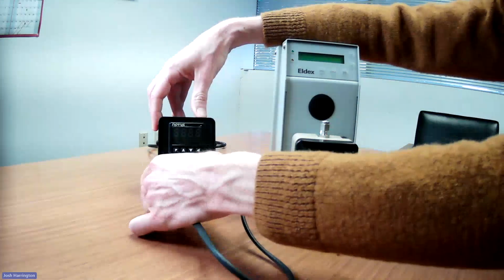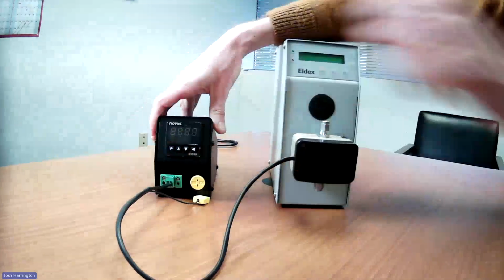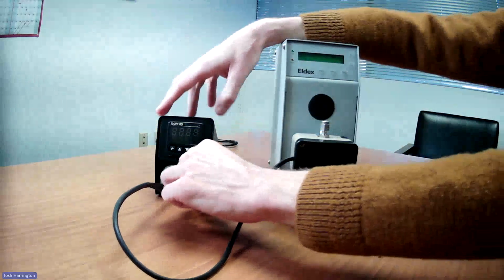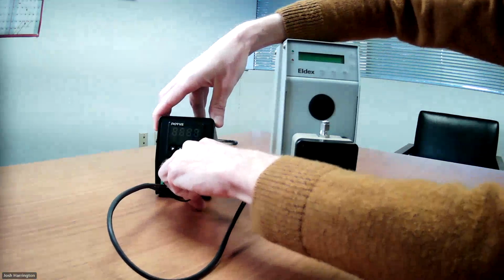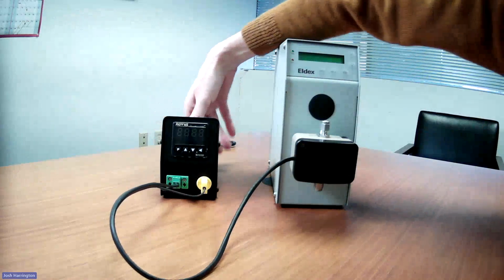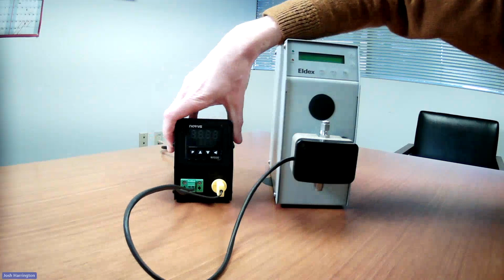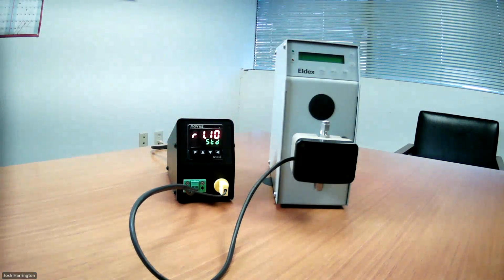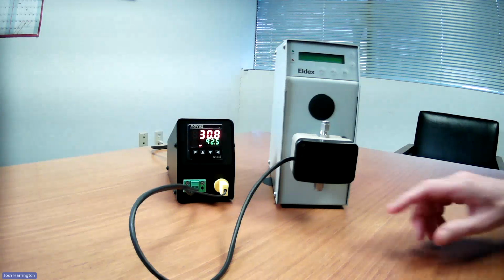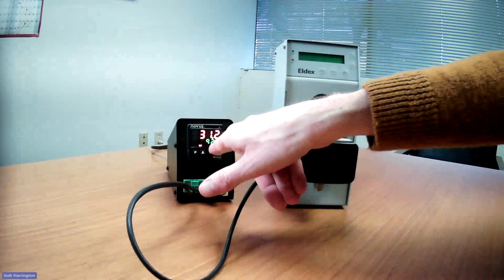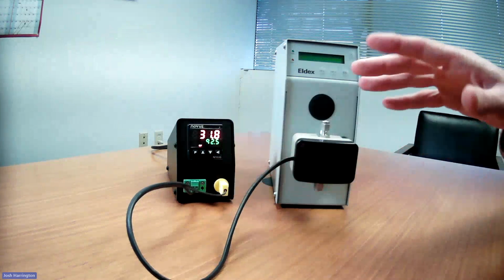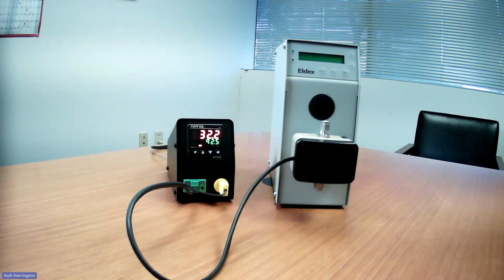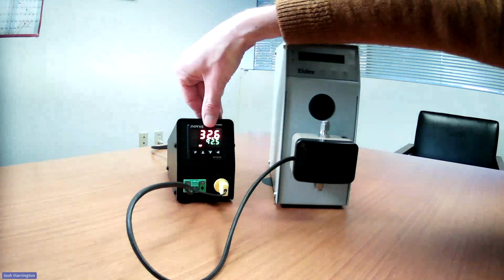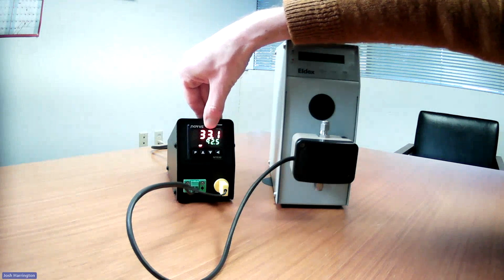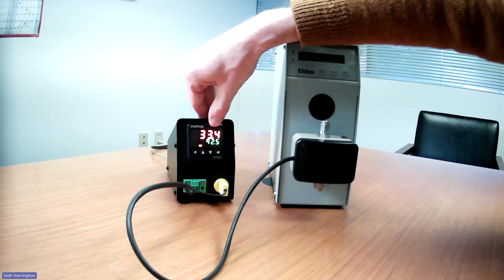So for the connection, first goes the power, then goes your thermocouple, and it's ready to go. So turn on the power switch on the back. There's a quick reset that has to happen. And then it's basically functioning as is. This device right now is set for 92.5 degrees Celsius. You can also change the settings on the display so it displays in Fahrenheit, and the actual temperature is here on the top. So you can see it slowly rising to the set point we have at 92.5.